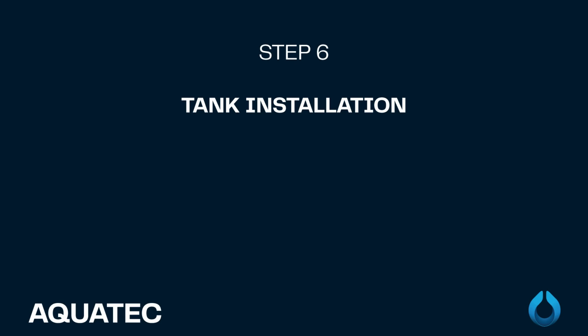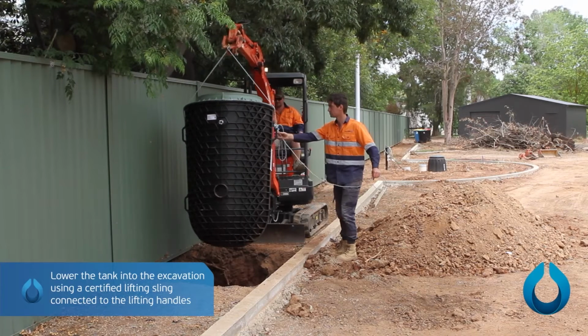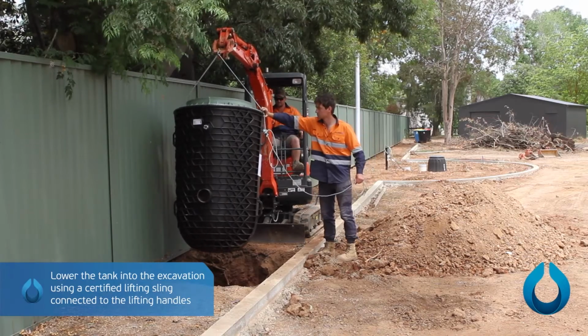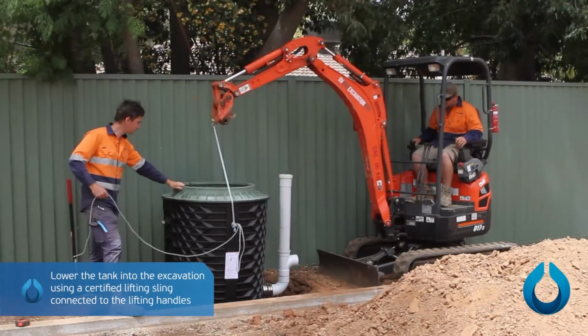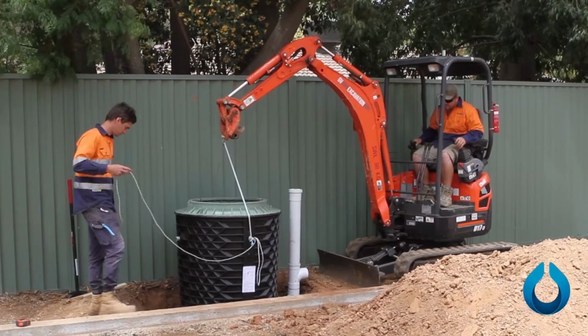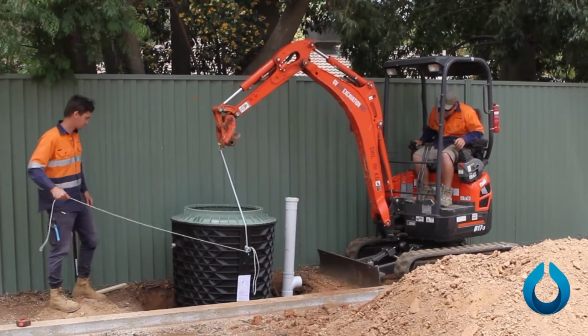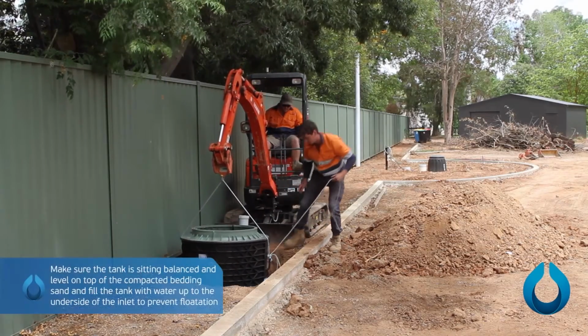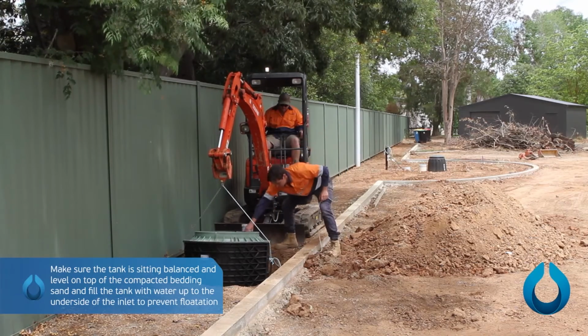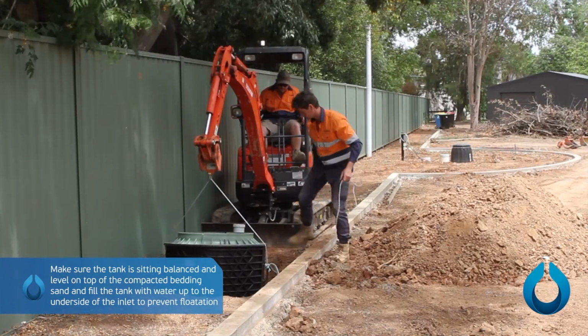Step 6. Tank installation. Lower the tank into the excavation using a certified lifting sling connected to the lifting handles. Make sure the tank is sitting balanced and level on top of the compacted bedding sand and fill the tank with water up to the underside of the inlet to prevent flotation.